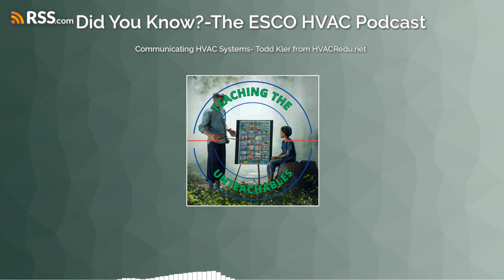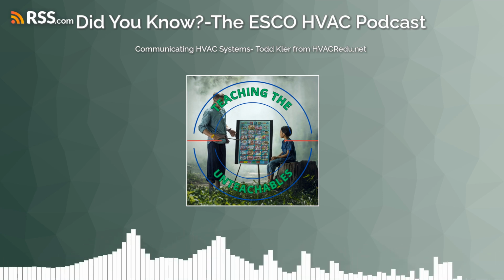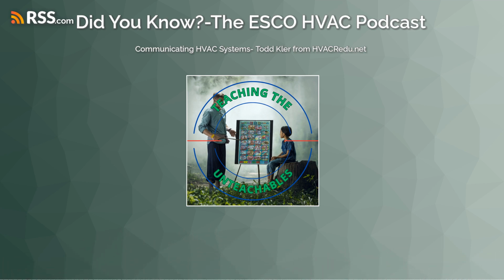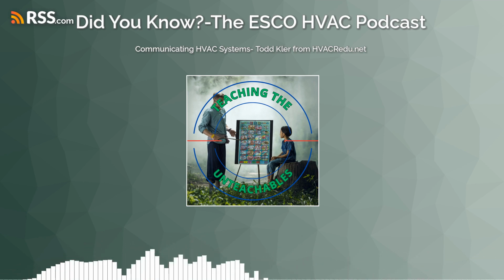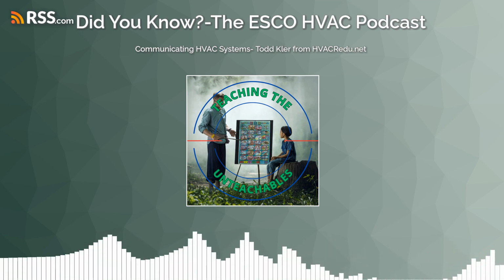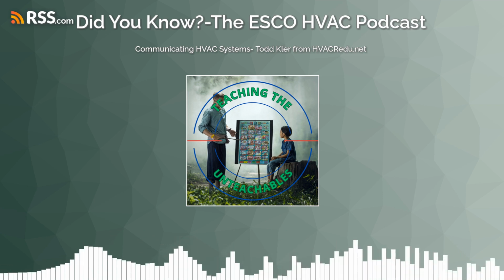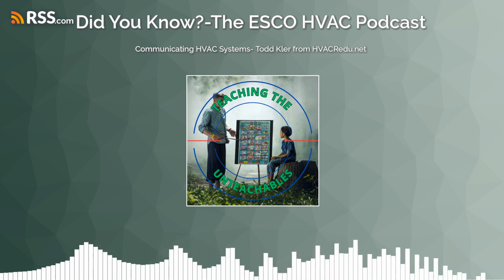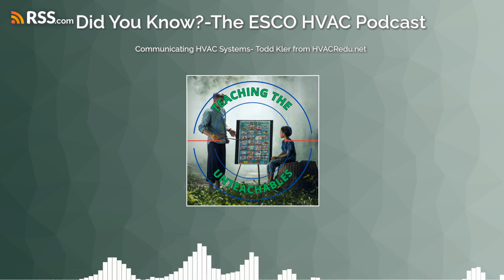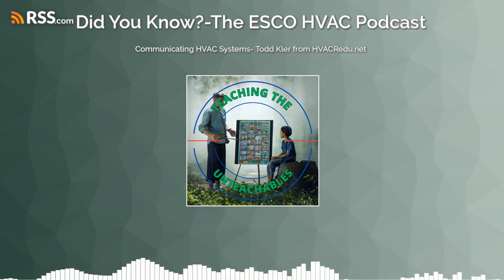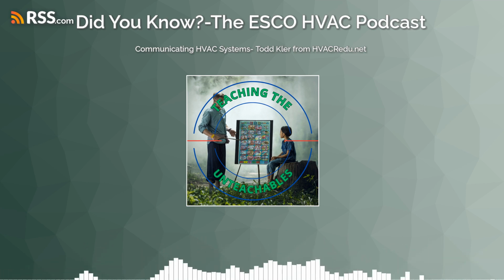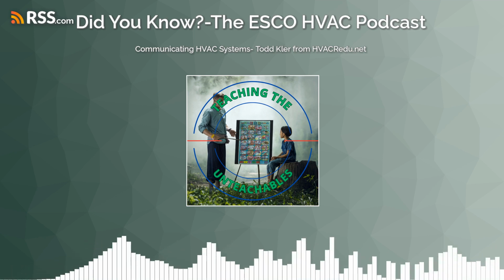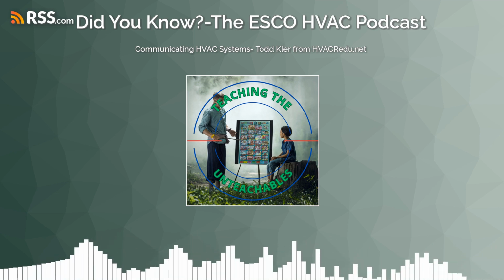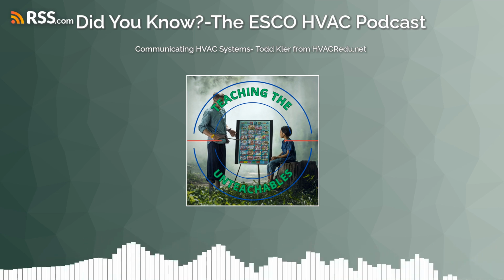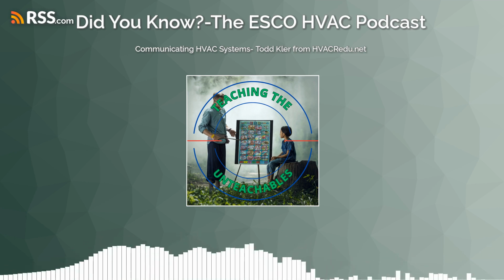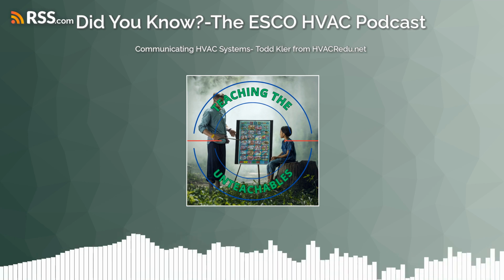At the indoor unit, we're checking A to common, we're checking B to common, outdoor unit, A to common, and B to common. And if you look at it, it's simply stating we've got a 3-volt DC power supply on these instead of a 5-volt DC power supply. And each manufacturer will be different. That's right. But it goes back to that protocol language. It does. How do we check them? We simply open up the service manual and verify the voltage. You're going to find that some of these look really similar to each other when we get into it.